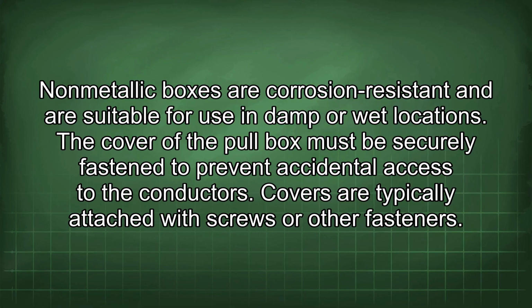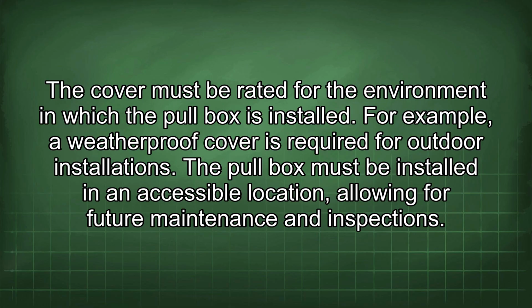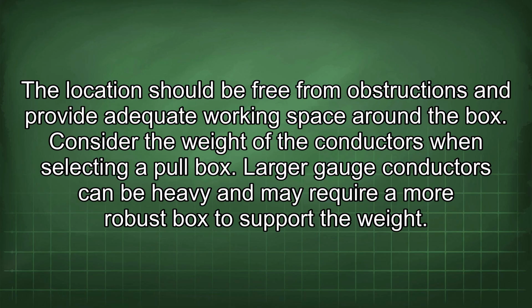Covers are typically attached with screws or other fasteners. The cover must be rated for the environment in which the pull box is installed. For example, a weatherproof cover is required for outdoor installations. The pull box must be installed in an accessible location, allowing for future maintenance and inspections. The location should be free from obstructions and provide adequate working space around the box.